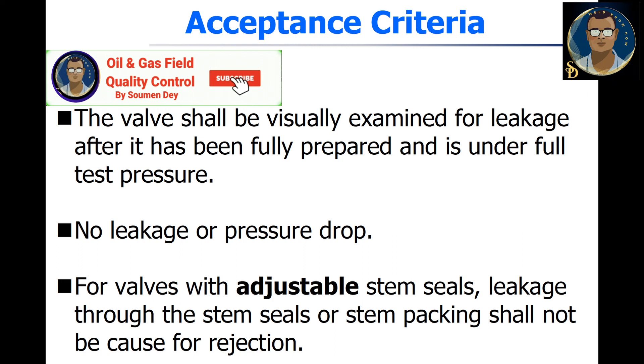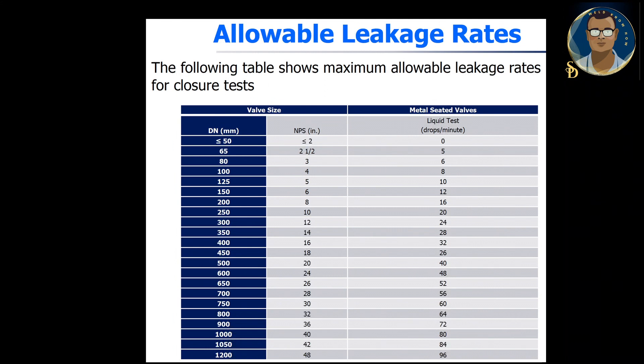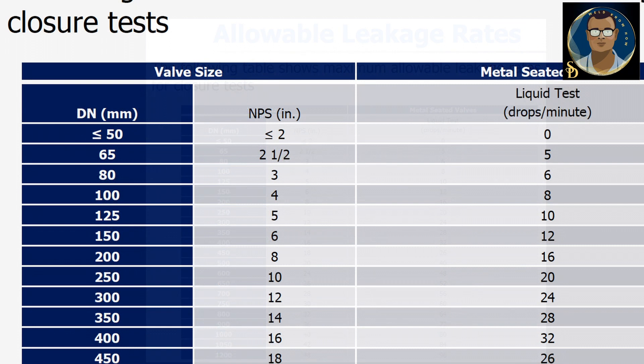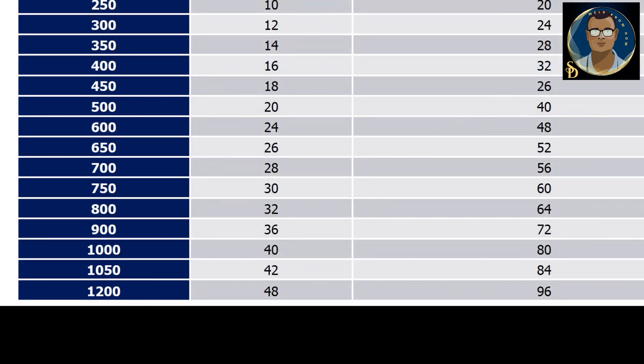Acceptance criteria: the valve shall be visually examined for leakage after it has been fully pressurized and is under full test pressure. No leakage or pressure drop is acceptable. For valves with adjustable stem seals, leakage through stem seals and stem packing shall not be cause for rejection. Regarding allowable leakage rate for closure or seat tests: for valve size less than 2 inch, zero drops per minute is acceptable. For example, for 10 inch, 20 drops per minute is acceptable, and for 48 inch, 96 drops per minute are acceptable.